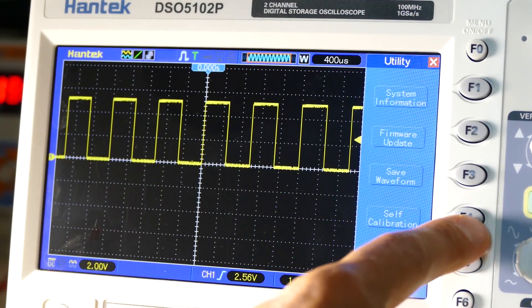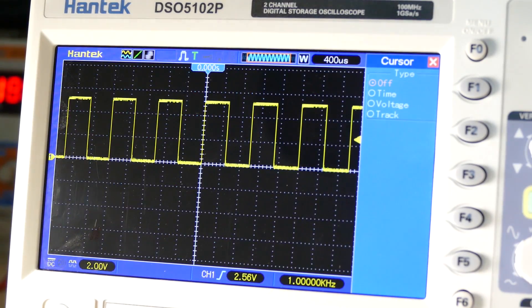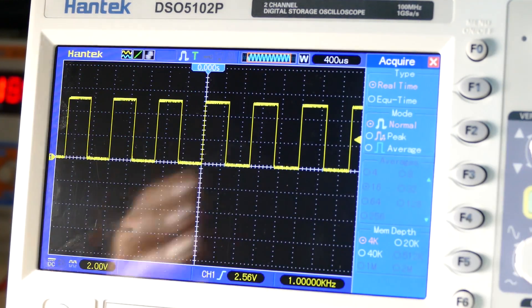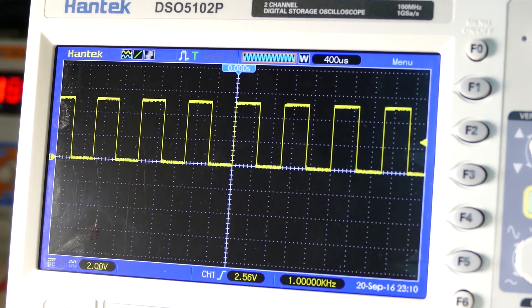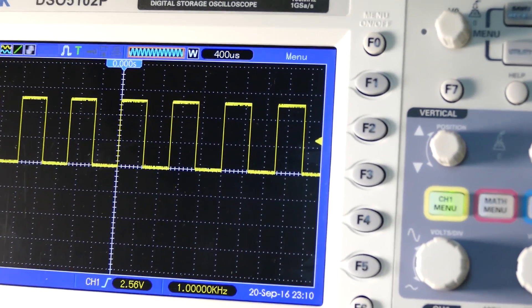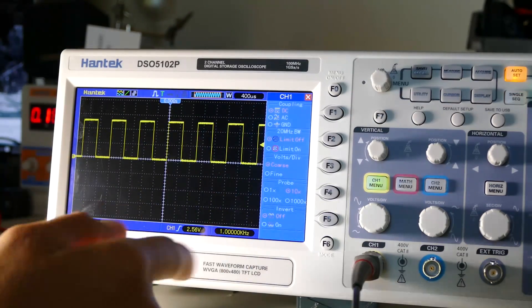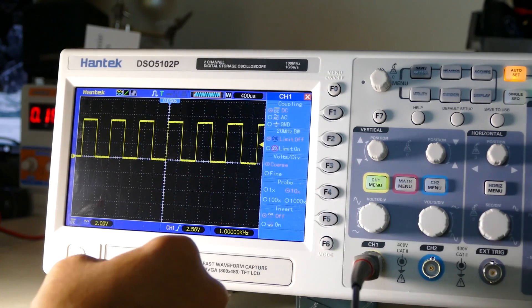Self calibration — I actually already ran through this, it takes about 5 to 10 minutes. Cursor, time voltage track. Acquire: real time, normal peak average. I'm just showing you guys some of the settings, not going to go too much into detail. If we hit the channel menu button, we can get coupling — DC, AC, or ground — and 20 megahertz bandwidth limit. Volts coarse/fine, probe 10 times.